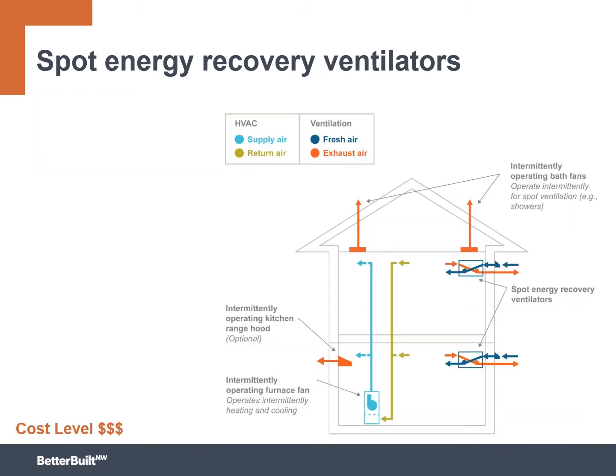With these spot energy recovery ventilators, it's a pretty tempting approach, right? Because a company like Panasonic makes some of these, what they refer to as spot ERVs, and they're relatively inexpensive for a single unit. The challenge is, again, as I just mentioned, to provide balanced ventilation, these devices are only capable of being balanced up to 20 cubic feet per minute. We're going to talk a little bit later about the actual ventilation needs of the home, or you can review the Build Tight Ventilate Right module, which actually goes into much more detail on that. But suffice to say, most standard mid-sized homes, 2,000 to 3,000 square foot homes, would need 2 or 3 of these devices to be put in.